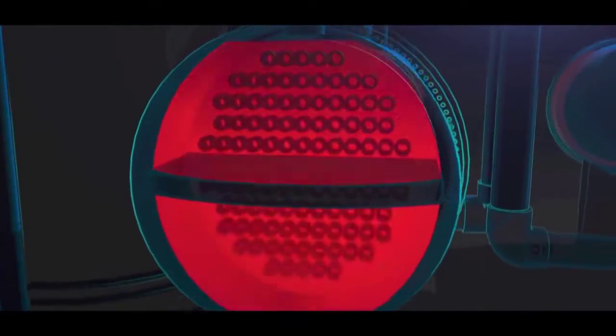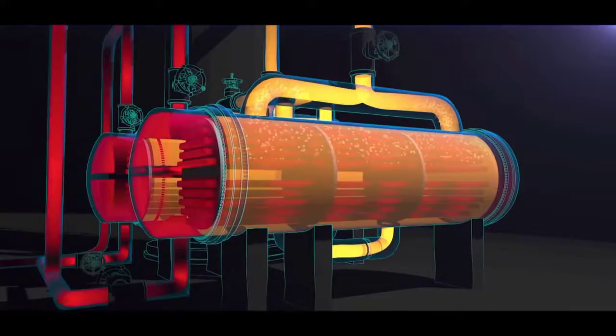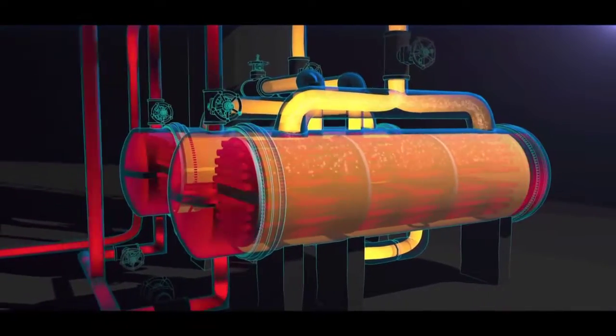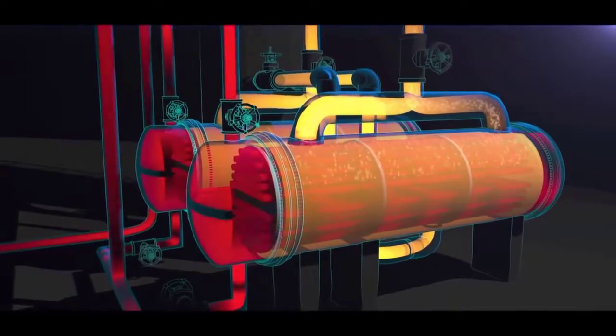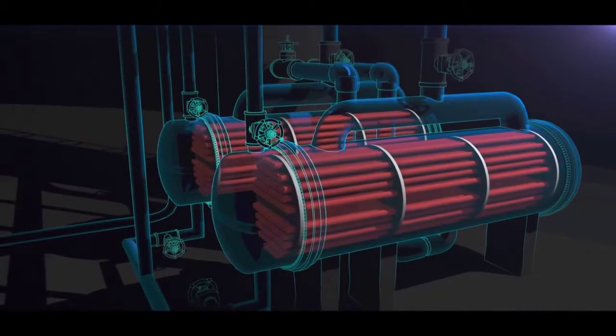earlier in the process. Over time, the oily tar from the water builds up on the walls of the reboiler tubes. This buildup is called fouling. Fouling reduces the efficiency of the reboilers. Periodically, the reboilers must be shut down to clean the tubes. The original propylene fractionator design had both reboilers running simultaneously. But in that configuration, the fractionator had to be shut down when a reboiler fouled and needed cleaning.